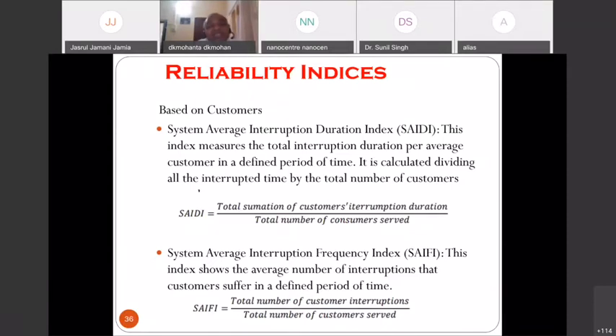So what are the HL3 or distribution system reliability indices? Here, the relative indices will be based on customers or load. A very famous index is called System Average Interruption Duration Index, or SAIDI. This index measures the total interruption duration for the average customer in a defined period of time. It is calculated by dividing the total interrupted time by the total number of customers - that is, the total summation of customers' interruption duration divided by the total number of customers served.